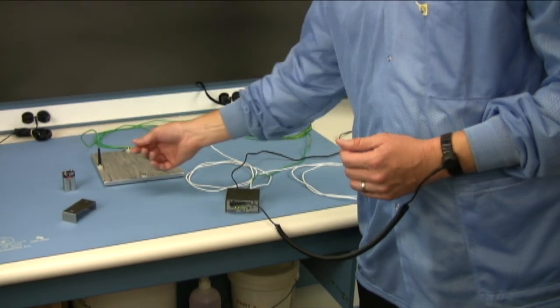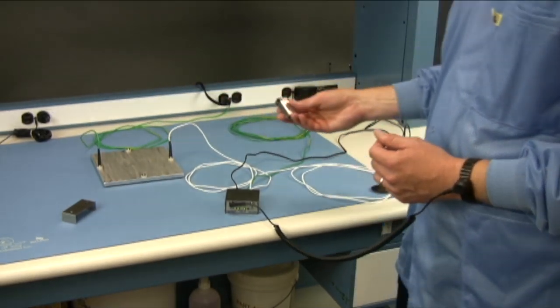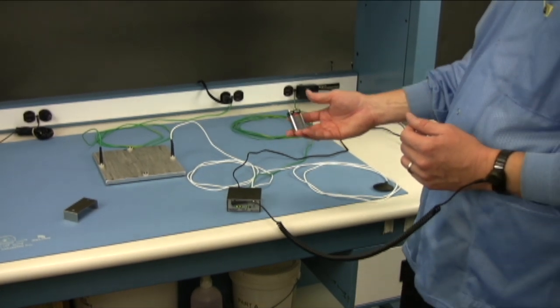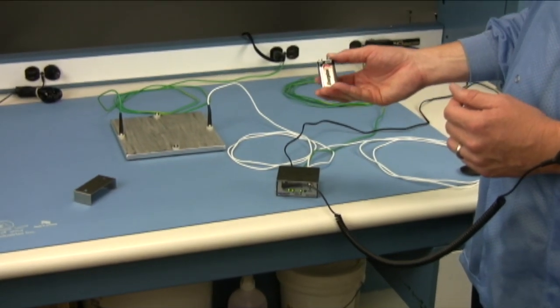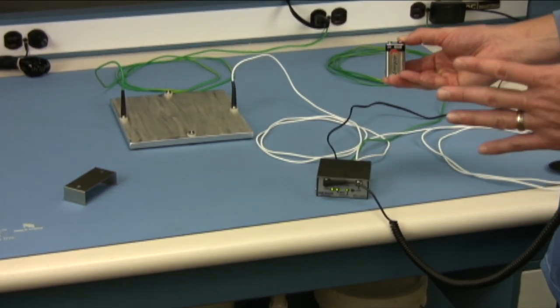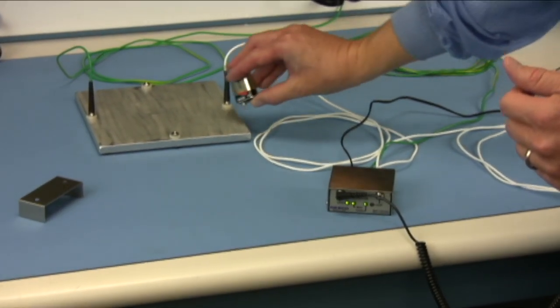We can demonstrate the voltage on the operator in excess of plus or minus 3 volts by using a 9 volt battery. While touching one lead with a finger, touch the other lead to a known ground. The induced voltage will cause the monitor to alarm.